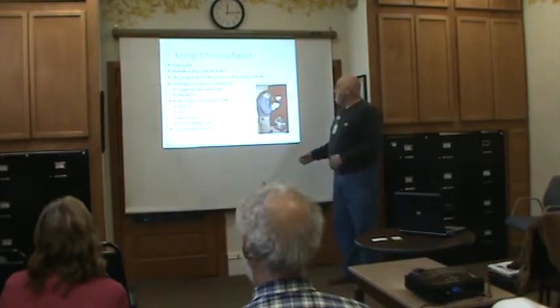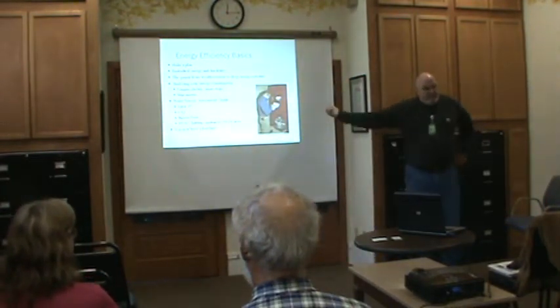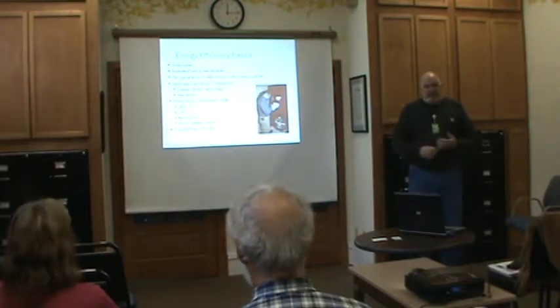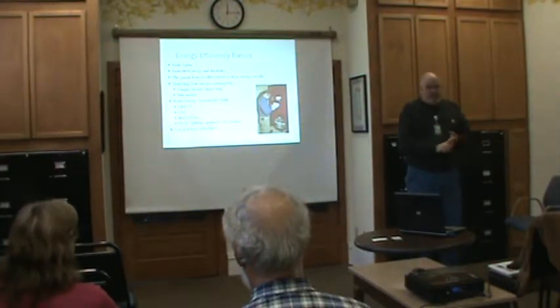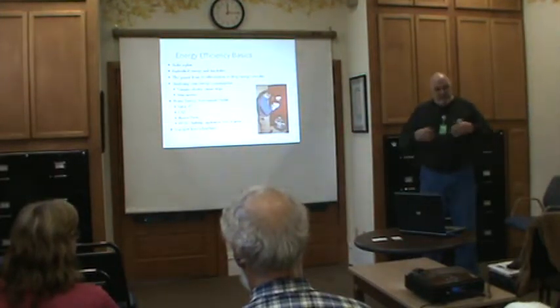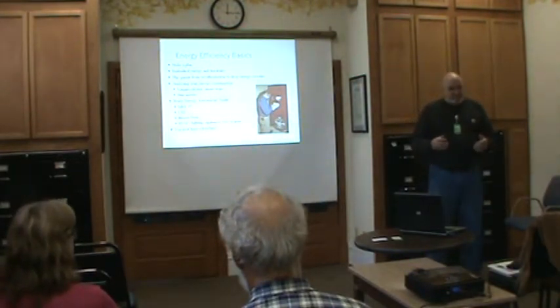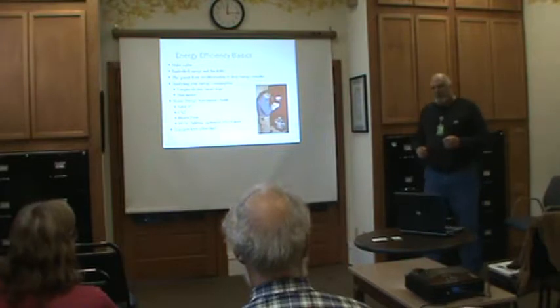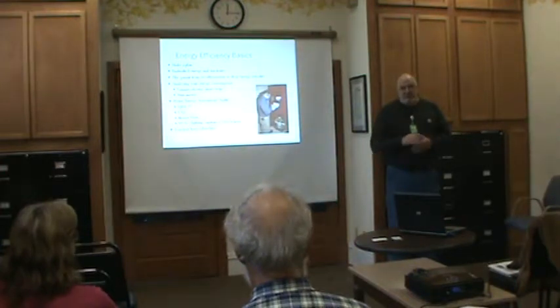And so home energy audit becomes a big part of understanding how your home works, because these are trained professionals who use diagnostic equipment like blower doors, combustion analyzers, sometimes infrared cameras, and other means and methods to seek out, measure, and find all the leaks in your house. They examine your naturally vented combustion appliances to make sure they're working right. So a furnace or a hot water heater with a flue that vents by gravity, etc. All those things are looked at before they deliver a report with a series of recommendations.